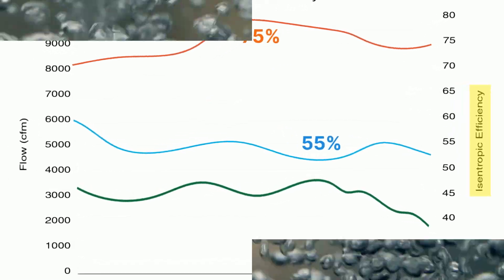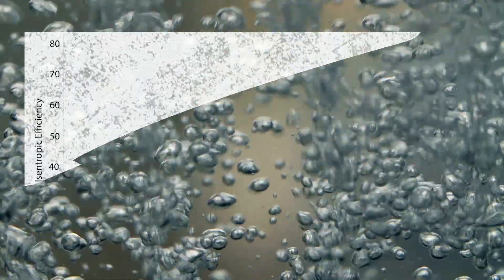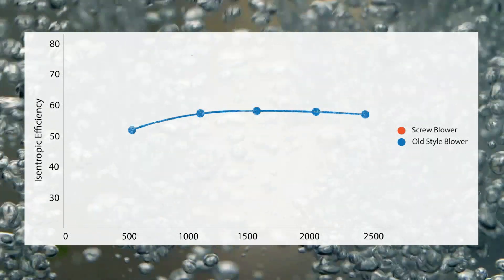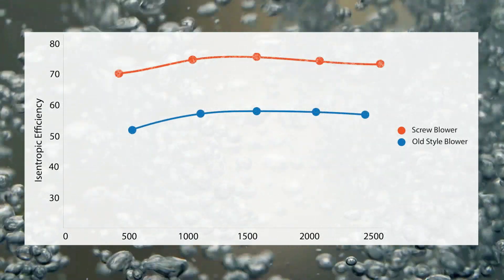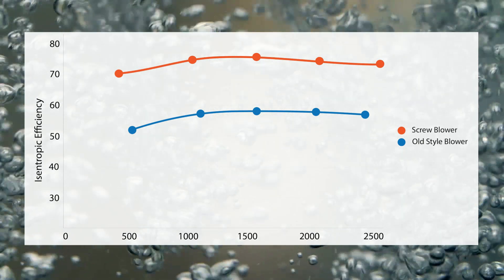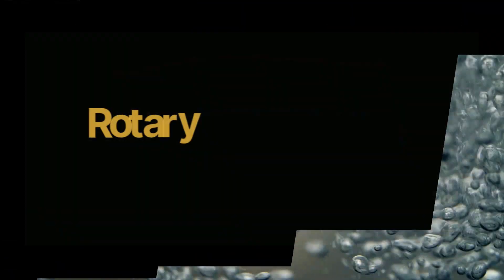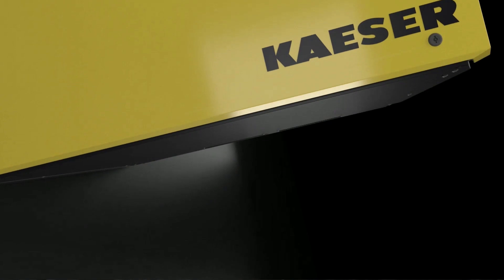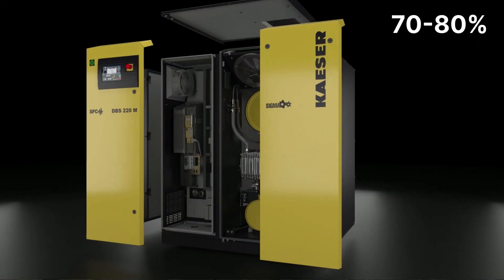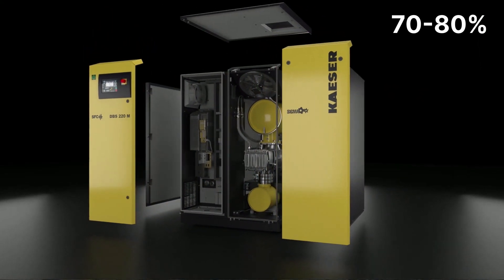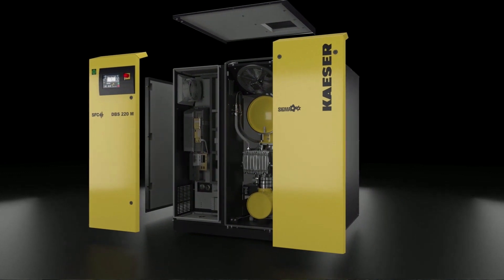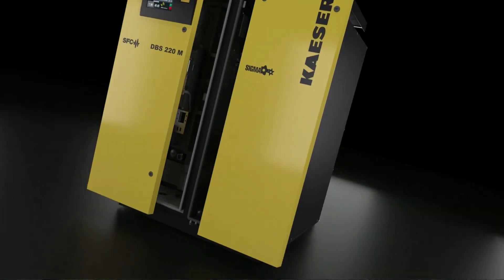While the isentropic power is easy enough to calculate, the actual blower power is a bit more difficult to nail down. Additionally, you want to evaluate the machine at multiple points across its control range. Modern blowers have a wide range with near-constant efficiency. They operate at 70-80% isentropic efficiency, while a traditional blower operates 50-60% efficiency.